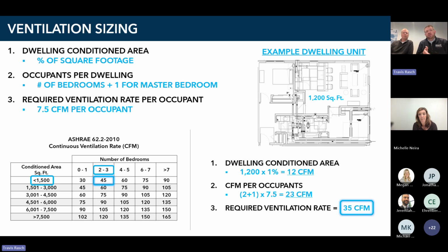If you use that table, what you're typically going to find is that the value is going to be higher. If you do the actual calculation, you'll see that number is typically a little bit lower. The reason I point this out is that if and when you're using the energy modeling side, you will find that even this small difference in ventilation rate, depending on your outdoor air conditions, may actually be more advantageous to use that lower ventilation rate. If it's a very cold day out, as an example, even that 10 CFM difference between this calculated value and the table value may add up as you get more units inside that building. You may find that using this calculated value is advantageous inside that energy modeling because you'll get less of a penalty, I'll say, due to the ventilation rate for these dwellings.